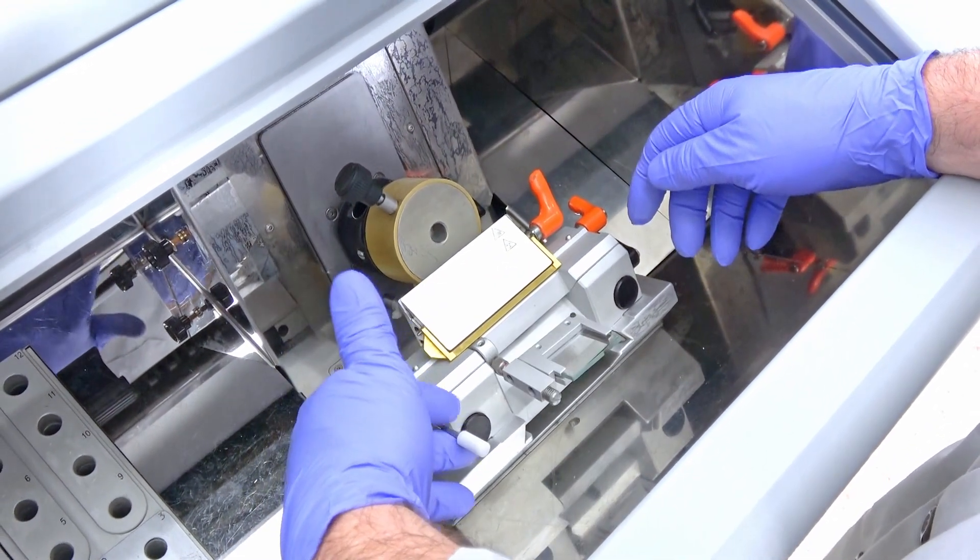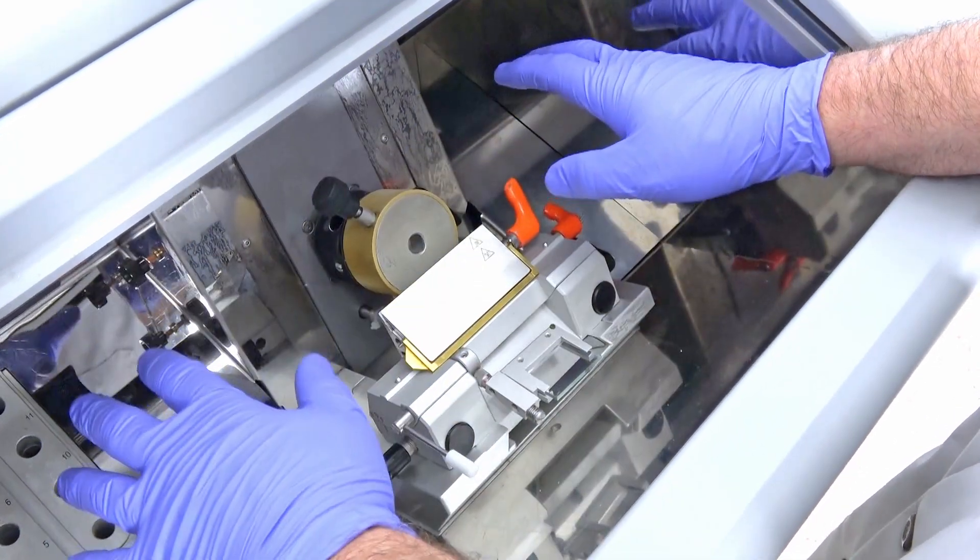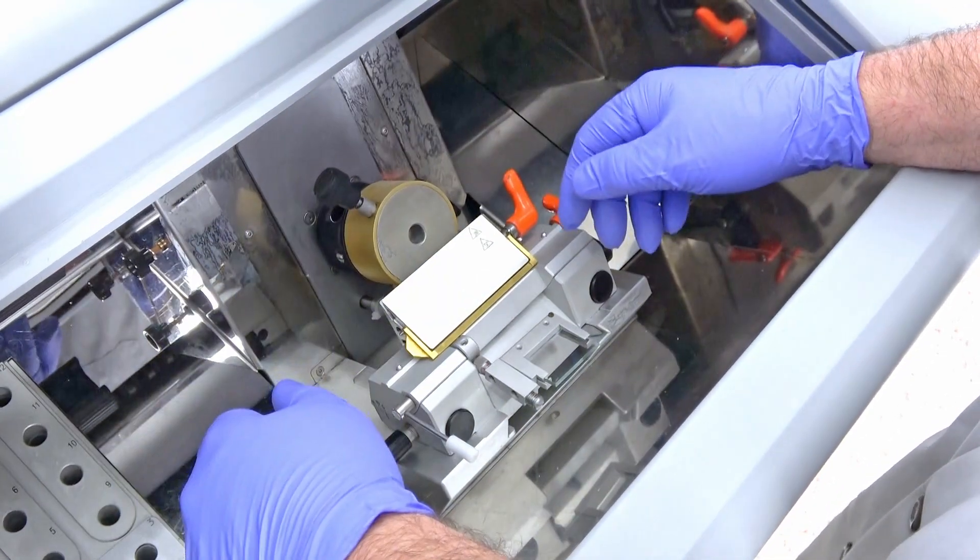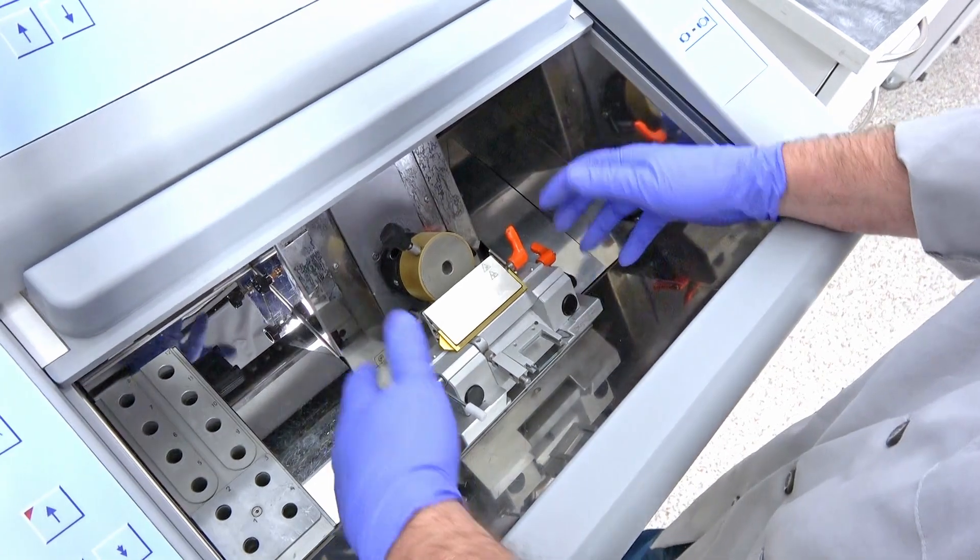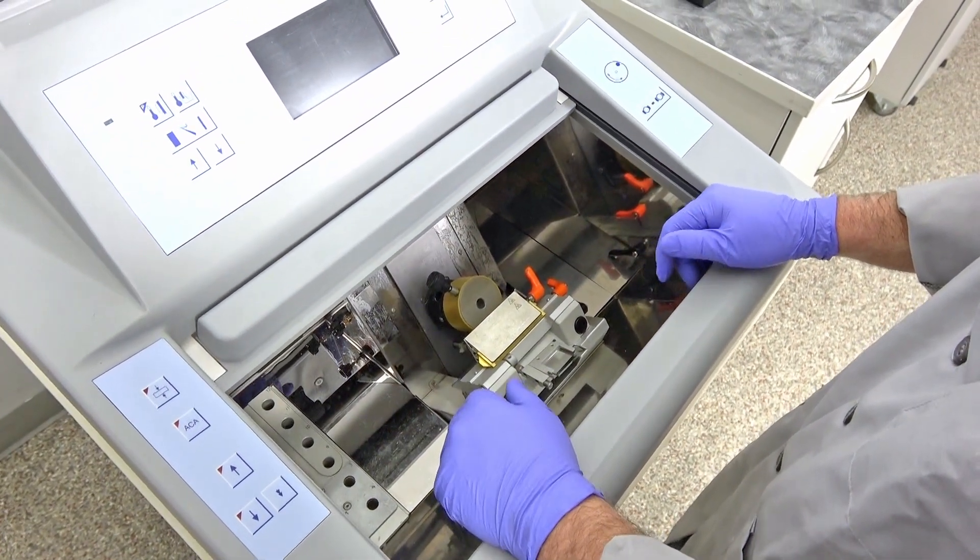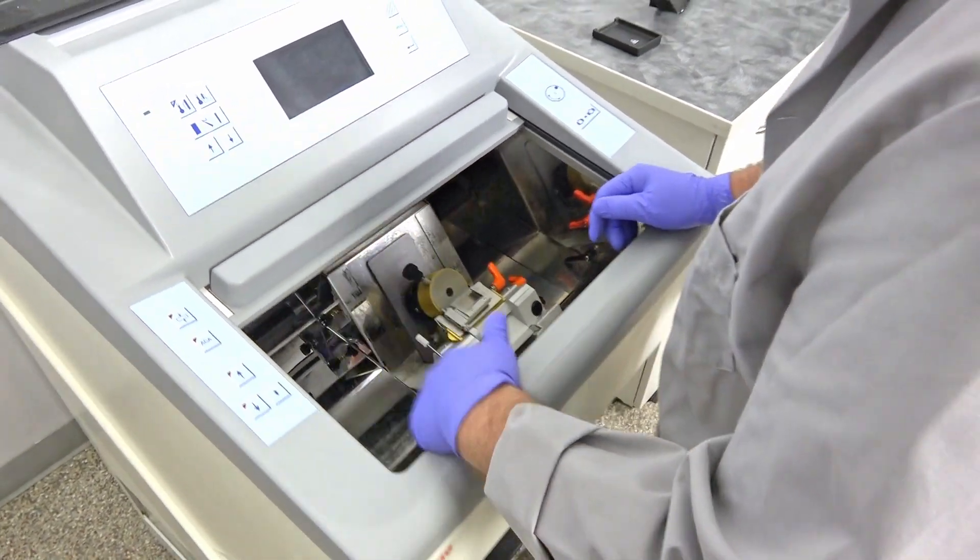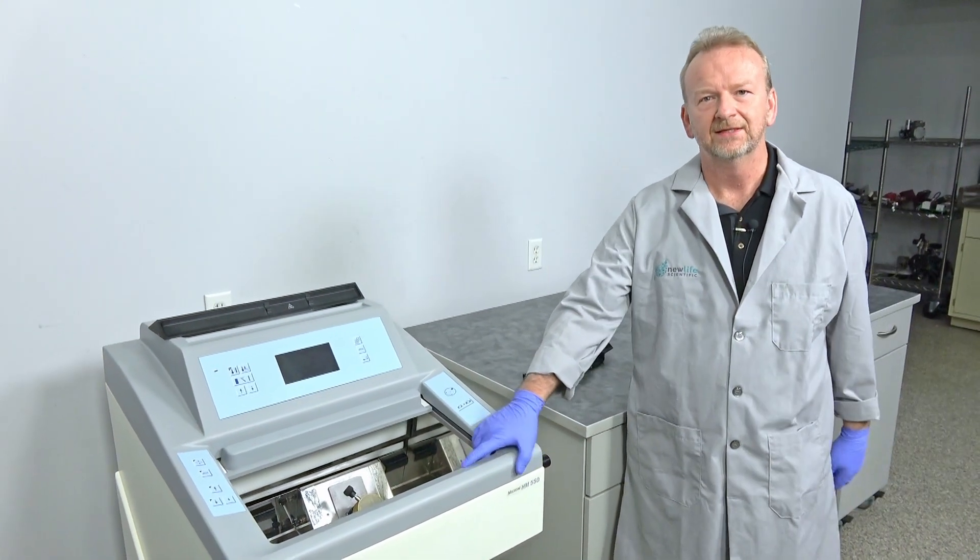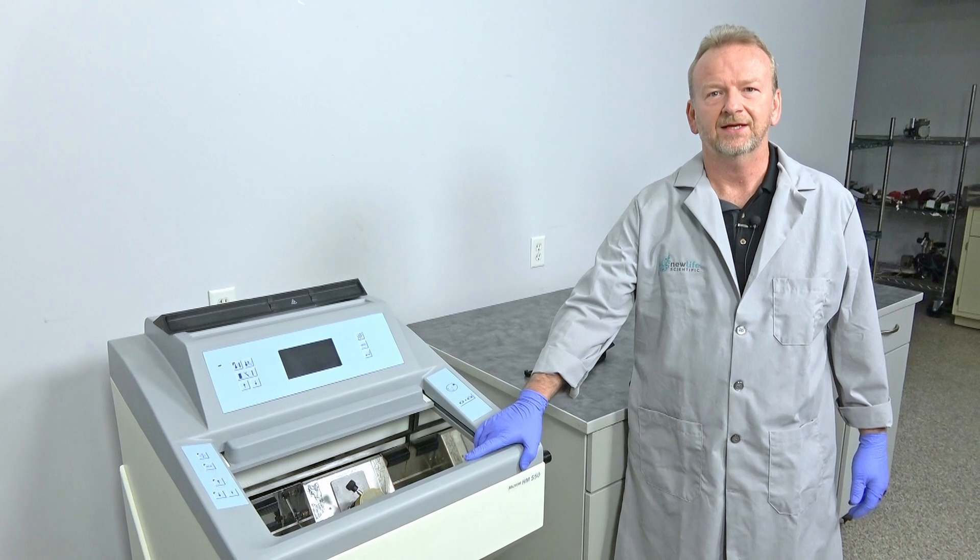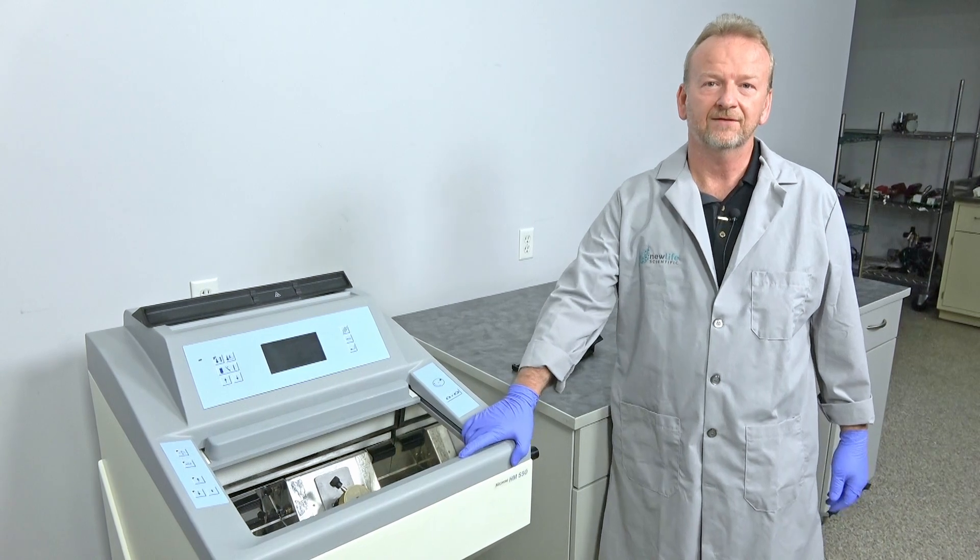Now you're back and ready to go. But like I said, this is really cold yet and I'm going to let this completely thaw out and then wipe everything down dry and make sure there's no moisture. I'm going to put it all back in before we start it again, otherwise this will all just freeze and none of the slides will work right. If you have any questions you can give us a call. We actually sell quite a few of the HM-550s and we have a really nice NX50 Cryostar that we just got in. If you have any questions give us a call here at New Life Scientific. Thanks for watching.